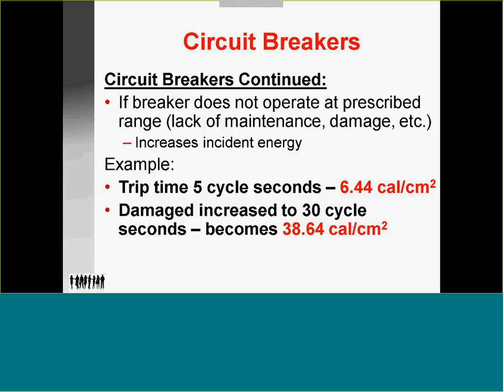Breakers. When you look at a breaker that does not operate correctly, due to lack of maintenance or damage, it increases energy and time. Now look at the situation. Circuit trip at 5 cycles at 6.44 calories. This is a category 2. Now, damaged, it increased to 30 cycles. We're at less than half a second difference, and look at the burn difference. 38.64. Category 4. I'm wearing a category 2 and I'm exposed to category 4. Survival is questionable. It'd be fatal or severe burns.